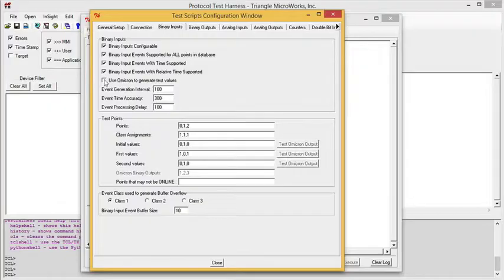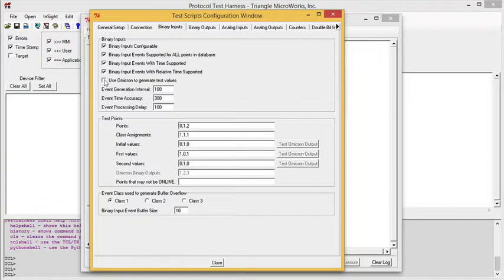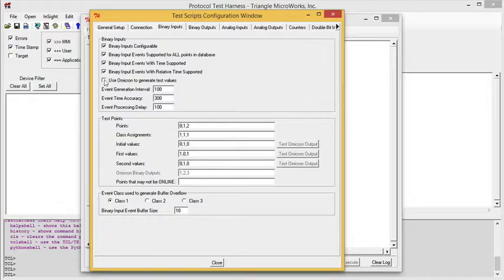If you don't have an Omicron to generate test conditions, the test harness allows you to use a custom TCL command to create a test condition, or to use DNP3 virtual terminal messages, or it will pop up a dialog box and instruct you what inputs to set up.